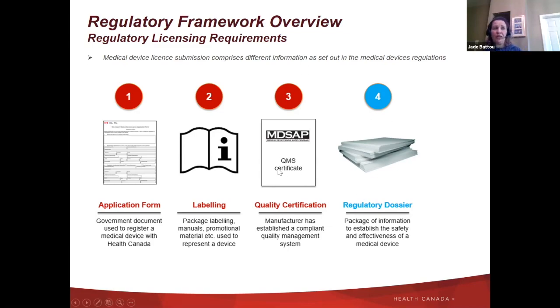In addition to these three parts, they have to pay fees. The fee depends on the risk of the device. As we go to class 4, the fee might go up to $10,000 per license, depending on whether it's an in vitro or non-in vitro device. Class 2 devices are up to $500 per file.